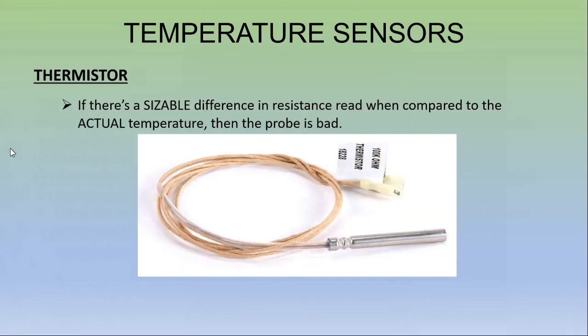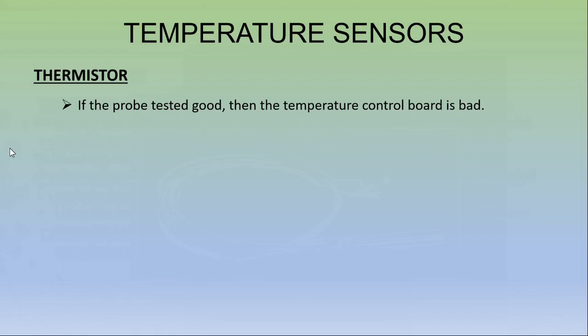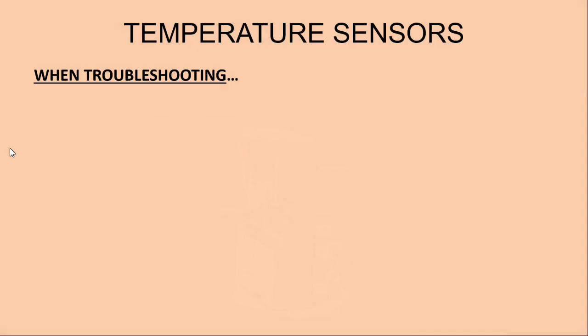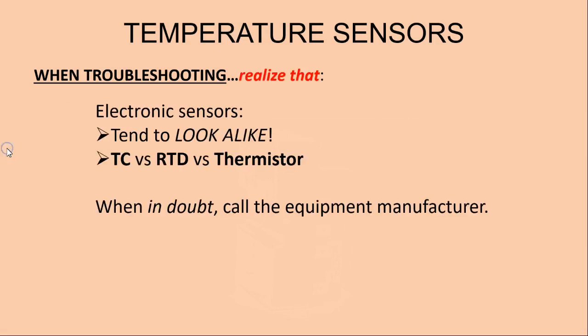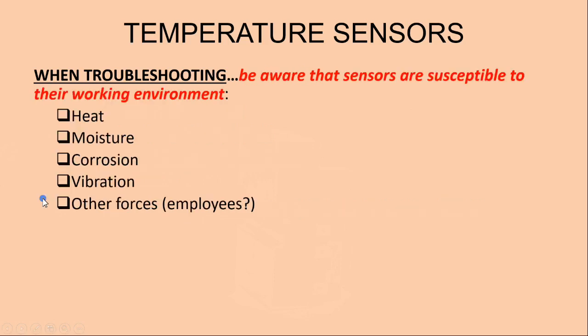All right, so when you're testing one, if there's a sizable difference in resistance read when compared to the actual temperature, then the probe is bad. If the probe tests good, then the temperature control board is bad. When troubleshooting electronic temperature sensors, here's some things to remember. Realize that electronic sensors tend to look alike. You have a thermocouple versus an RTD versus a thermistor. Which one is it? Well, when in doubt, call the manufacturer.